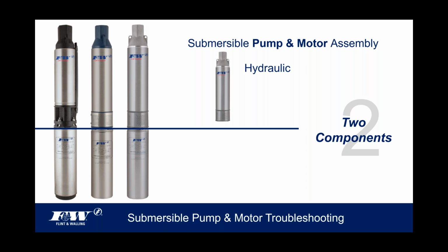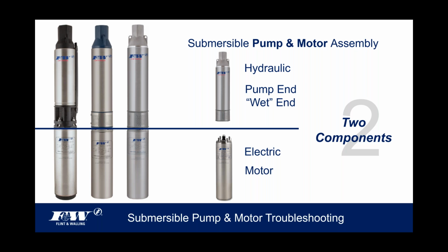Of course, there's the hydraulic side of this assembly, which is the pump end, and some people also refer to this as the wet end of the pump. Within that pump end is a series of impellers and diffusers, and this is the portion of the pump that has the responsibility of all the hydraulics, moving water, pressurizing it, and so on and so forth. On the bottom side is the electric side of this assembly, and that's your motor down there.